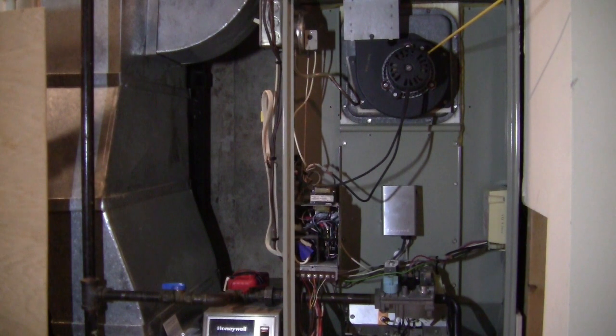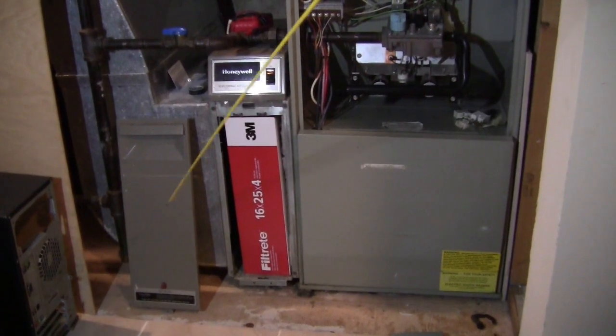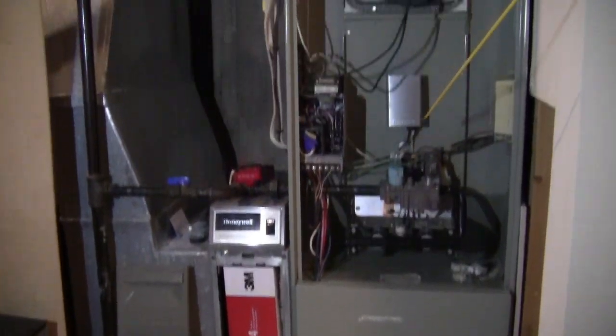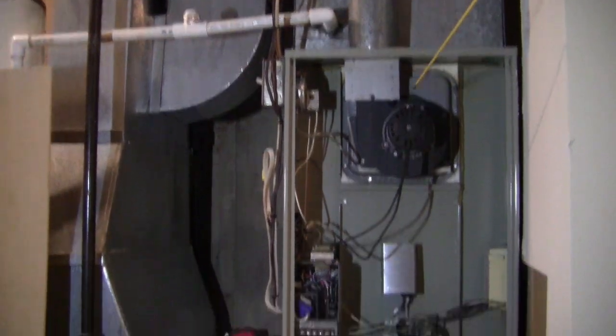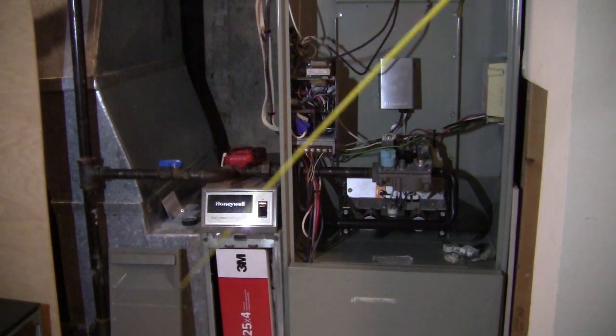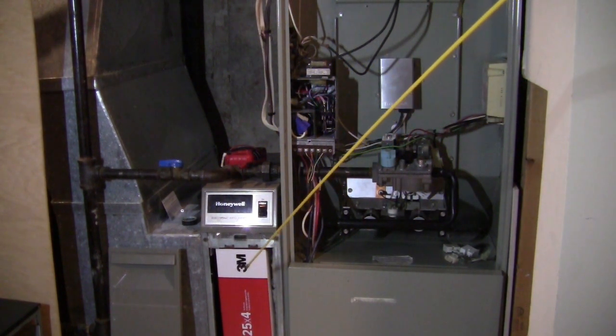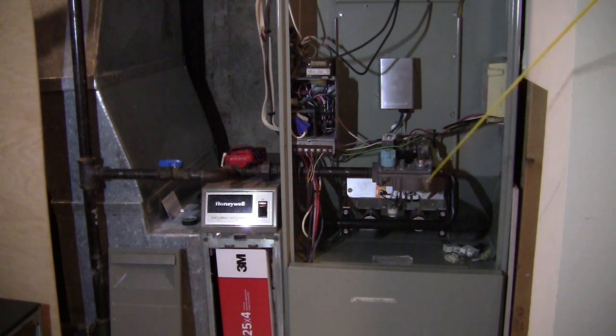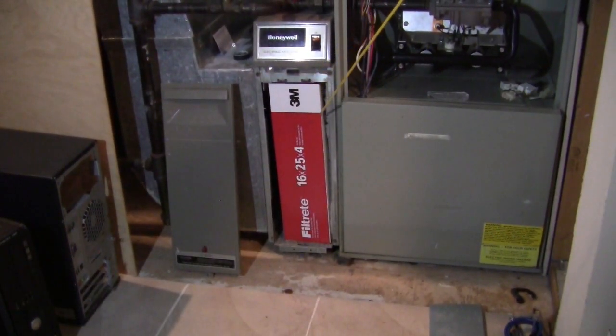The second thing is what? The circular air. The air actually comes from here, goes up to here. And this circular air has to be good. It has to be running. It has to have air pressure to push the air through. What kind of situation can cause this air to not circulate? There are multiple reasons. The most silly reason, and you can check some of the professional service people complaining about it, is that people don't change their air filter.